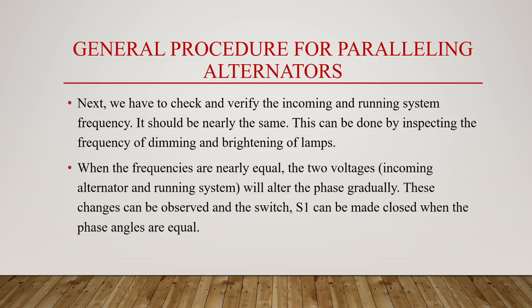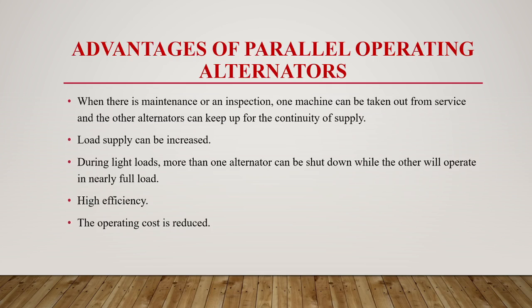So we have to check and verify the incoming and running system frequency. It should nearly be the same. First we have checked the phase sequence. Now we have to check the incoming and running system frequency. This can be done by inspecting the frequency of dimming and brightening of the lamps. When the frequencies are nearly equal, the two voltages, that is the incoming alternator and the running system, will alter their phase gradually. These changes can be observed and the switch S1 can be closed when the phase angles are equal.